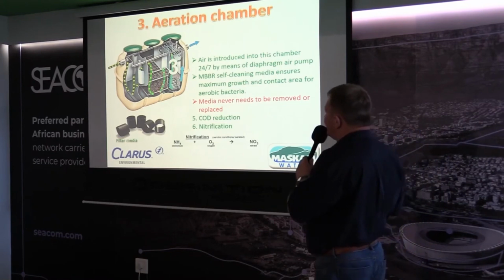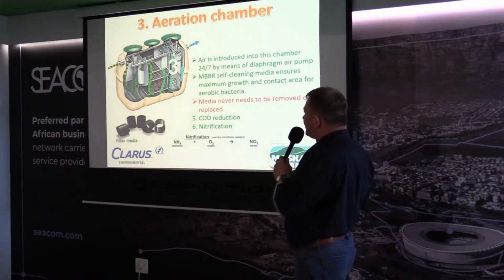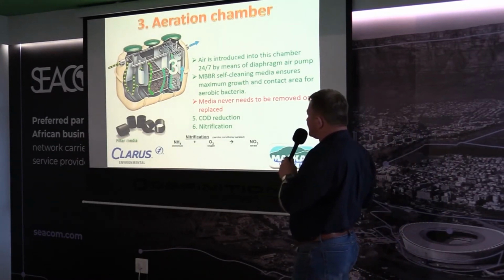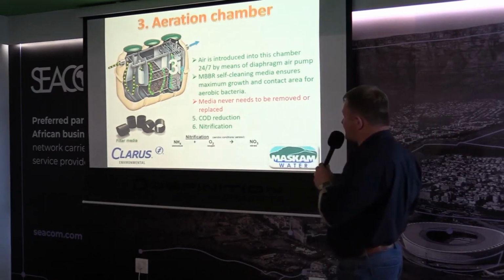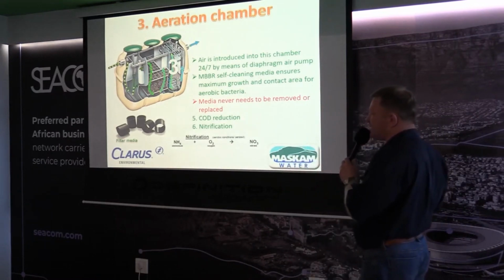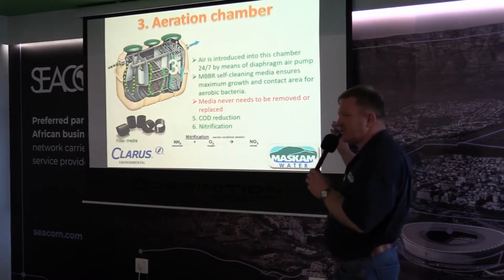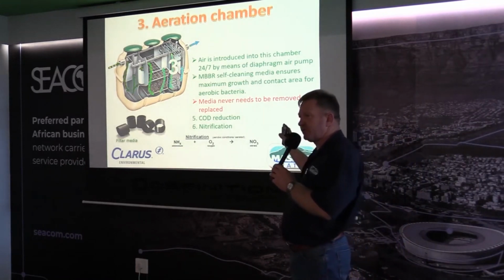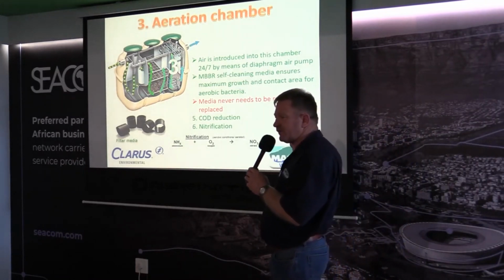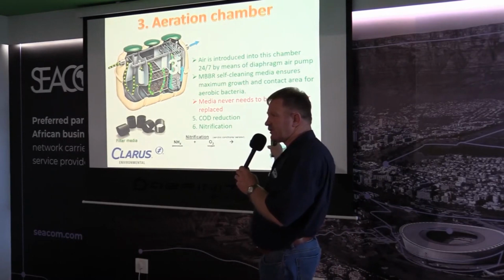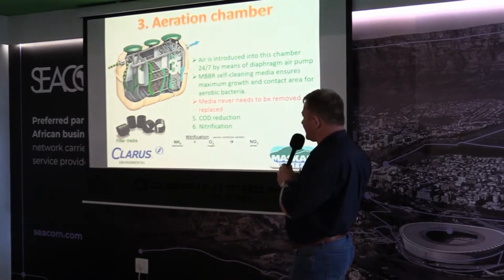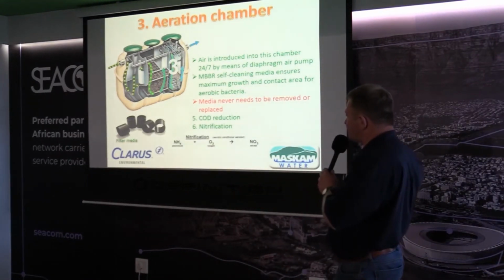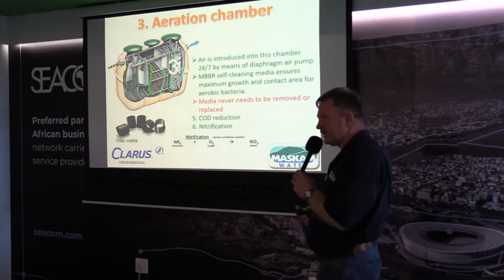Sorry. The aeration, as we said, COD reduction, nitrification taking place. And this is where most small plants' treatment stops. You will see a few more steps in this specific one, but this is where most stop. So you now still have a nitrogen problem because you've got ammonia, first changed to nitrite and then nitrate, but you still have the same amount of nitrogen in the system.